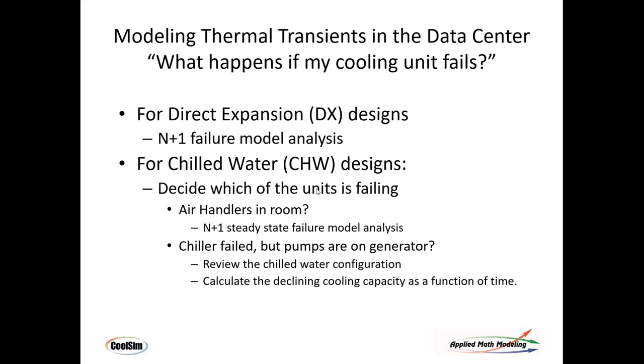For chilled water systems, things are a bit more complicated. If you want to study a failure mode where the air handler in the room fails — in chilled water systems you just have a fan coil sitting in the room — the same N+1 cases can be done in CoolSim by switching off one unit at a time in a round-robin fashion. I encourage those doing design to look at all of them, because geometry and location make a difference — air handlers don't all reject the same amount of heat.